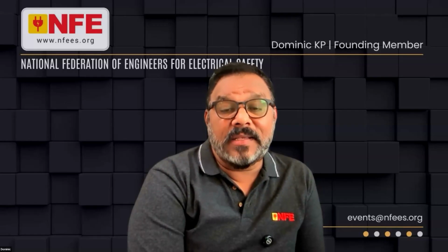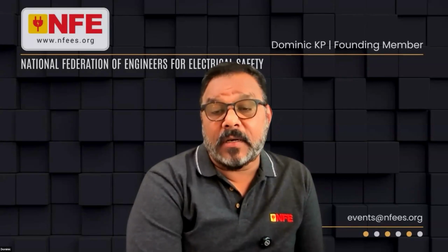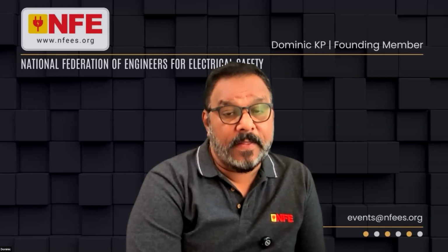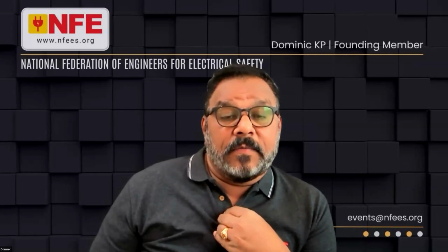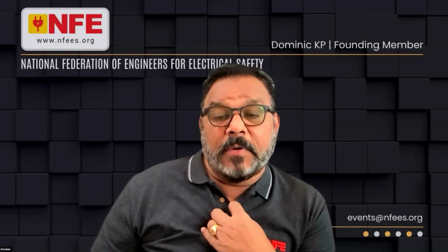Ganupesh is asking, are there any sensors installed in the cable to know real-time error or heat-related issues? In conventional outdoor and indoor terminations, no sensors are there right now. Nowadays a few companies are doing temperature measurement or PD activity patches on the termination. In GIS, the gas-insulated switchgear, a voltage detector kind of thing is there. Those kinds of sensors are there, but 99% of customers are not using sensors in terminations. Abhishek is asking, what is the easiest way to find an underground cable line fault?